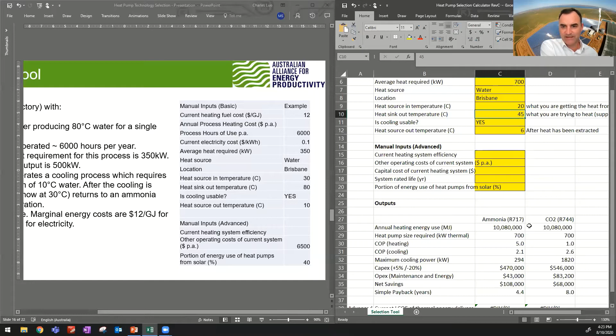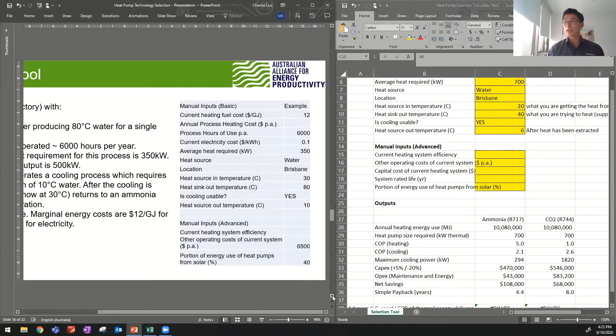There's a theoretical limit that we've put in just to be a bit conservative. But it is feasible for COPs of 6 with low temperature lift. So this is a fairly low temperature lift, from a heat source temperature of 20 to a heat sink out temperature of 40. And this is a dream scenario for a lot of ammonia heat pumps. So I'll move on to the next one.